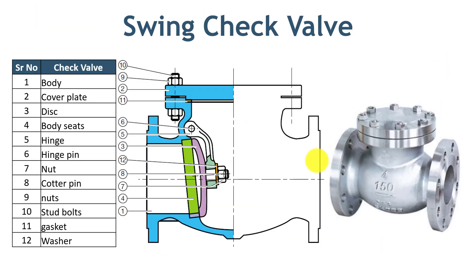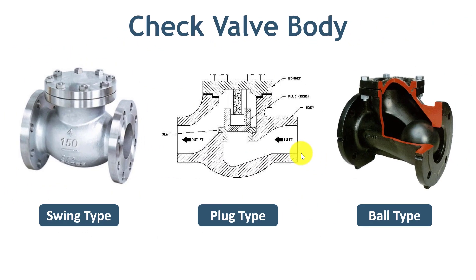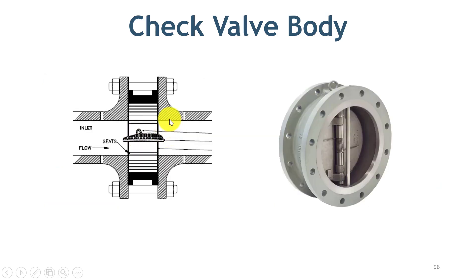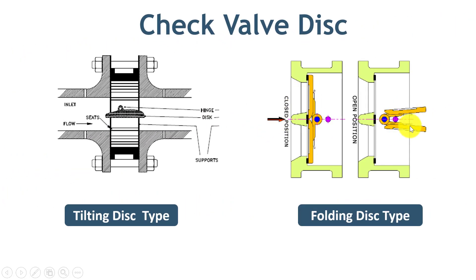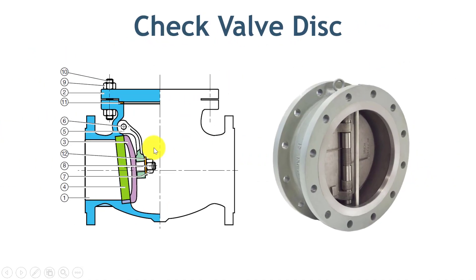Now let's quickly look at other parts of the check valve. You can observe that the body of the swing type, plug type, and ball type check valve is globular in shape. Whereas in the case of the dual plate and tilting disc check valve, it is a short cylindrical shape that resembles the body of a butterfly valve. In the check valve, the disc can be a single plate, such as in the swing type and tilting disc type. In the case of the folding type, the disc comes in two pieces. The shape of the disc in a ball and plug check valve is self-explanatory.